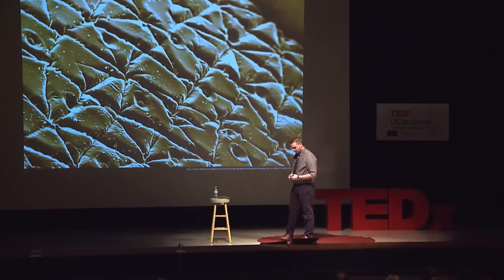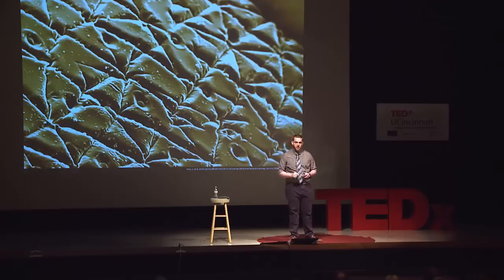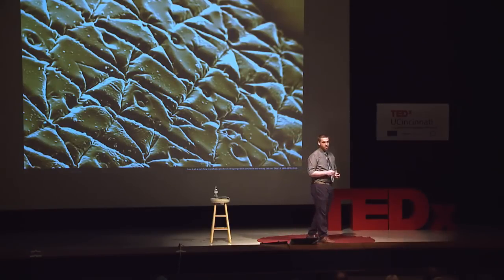This particular image is a replica of a grad student's skin — this is not real skin. This is plastic, fake skin that has a similar tactile feel, and it also has the ability to sweat. What a lot of people don't realize is if you're testing skin devices, you've got to do human subjects testing — put something on skin, which requires people, paperwork, and a lot of money. However, if you have an artificial skin, you no longer need that. You can do the same test for cents on the dollar and in half the time.